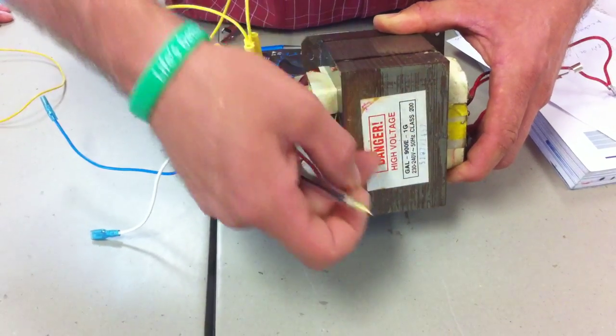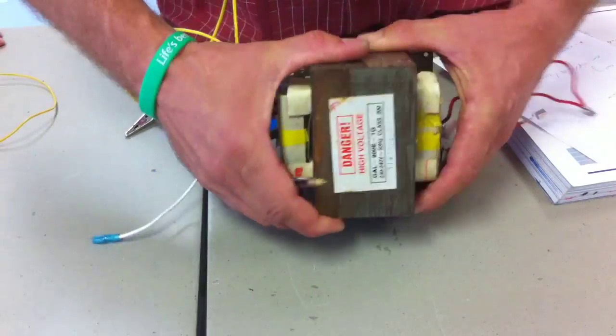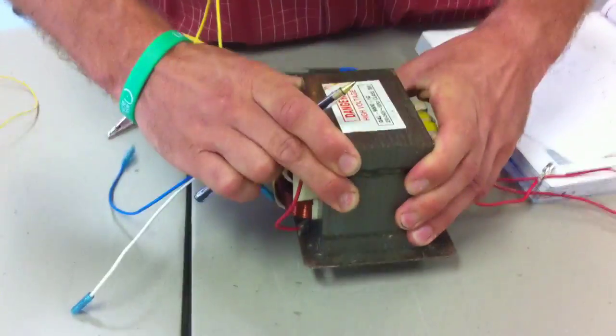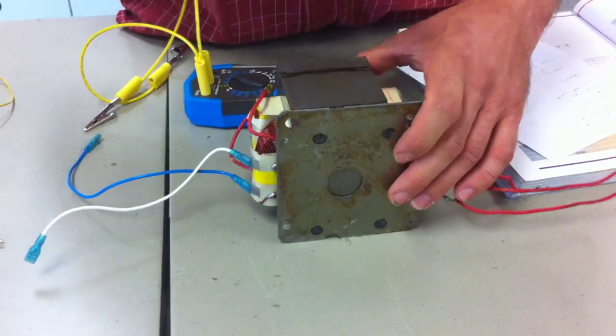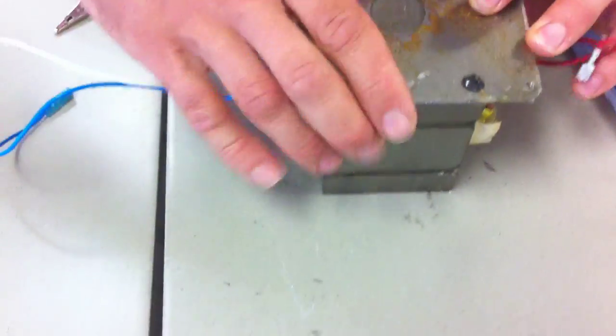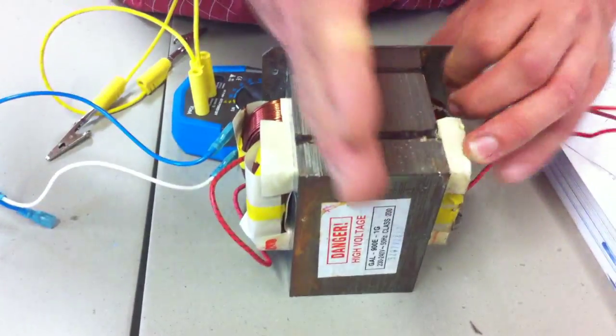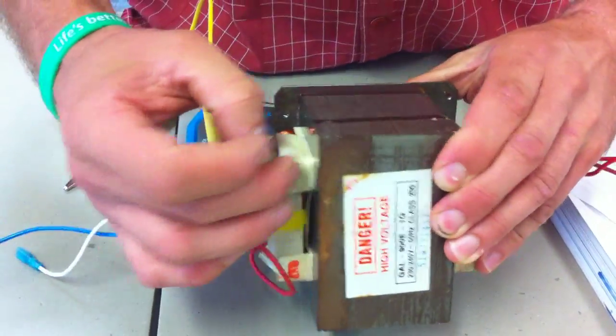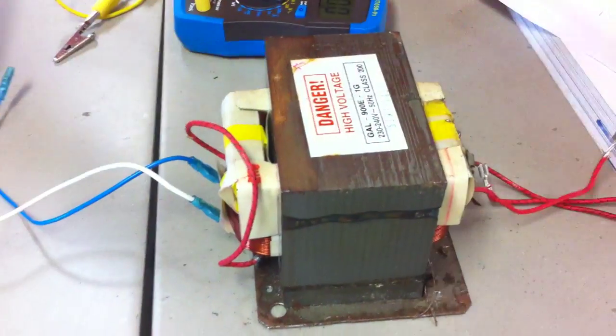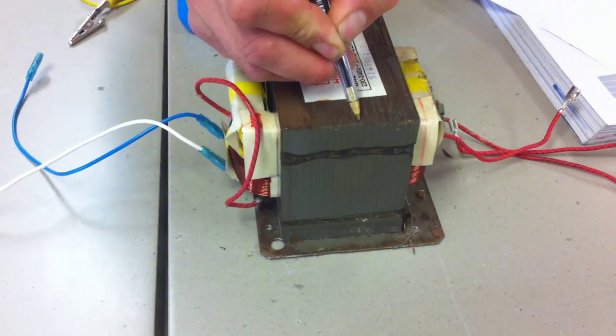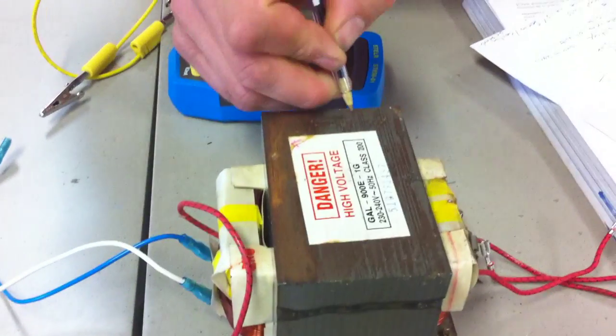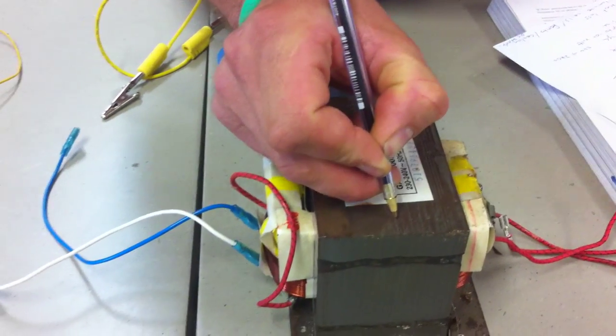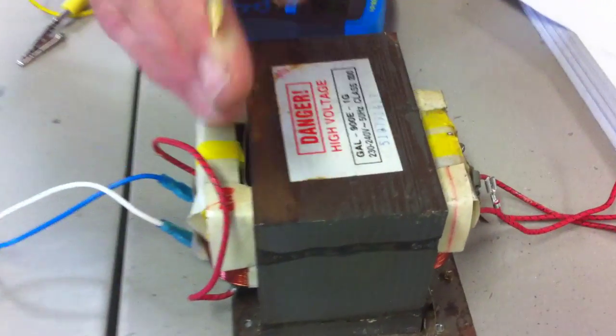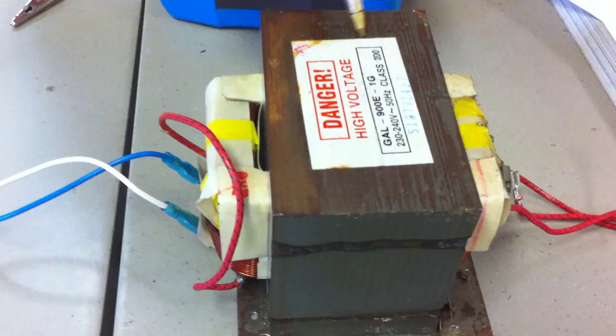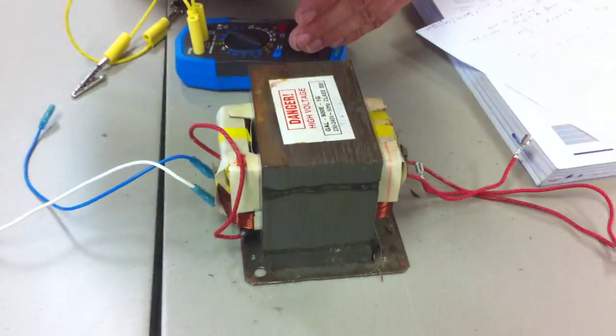That electrical eddy current would normally make this core very hot. So what they've done is make the core out of laminated steel, right through it, you can see it around there and underneath. Each plate is insulated from the next, so the only way an eddy current can run is up one very narrow plate, across it, and then all the way back down the other side.